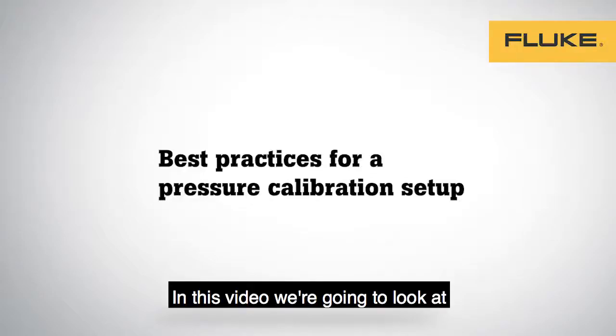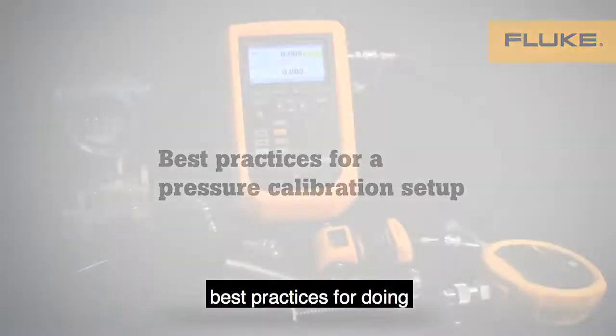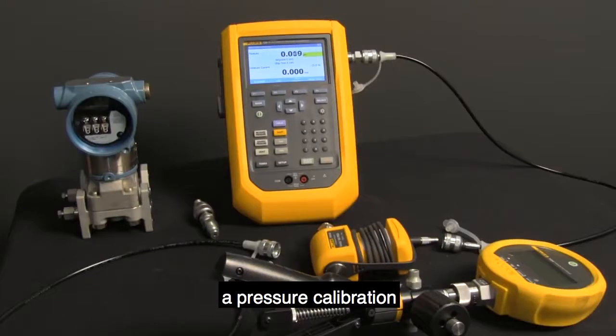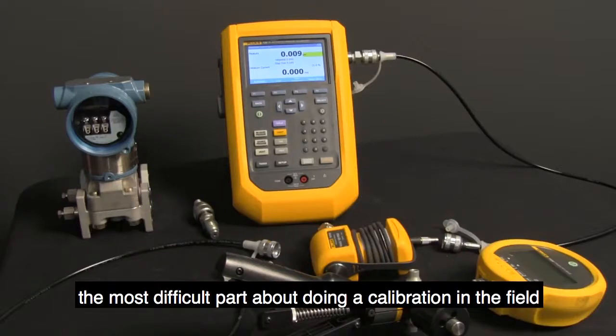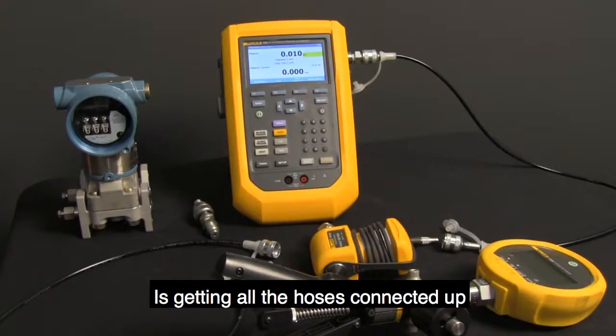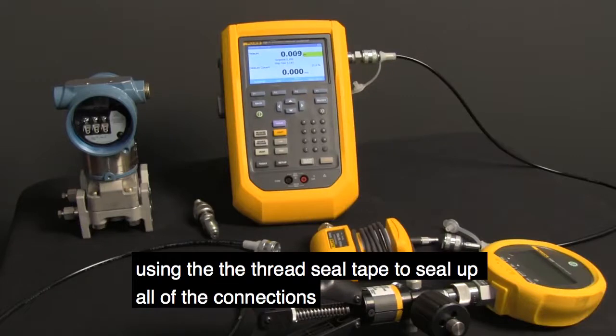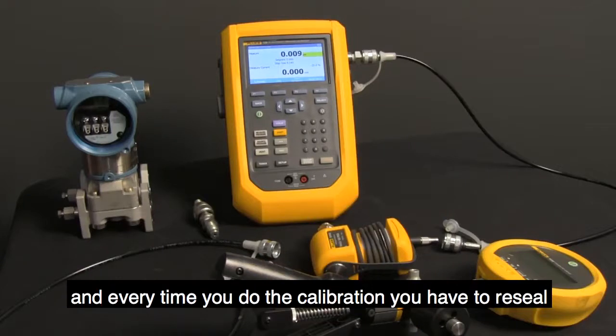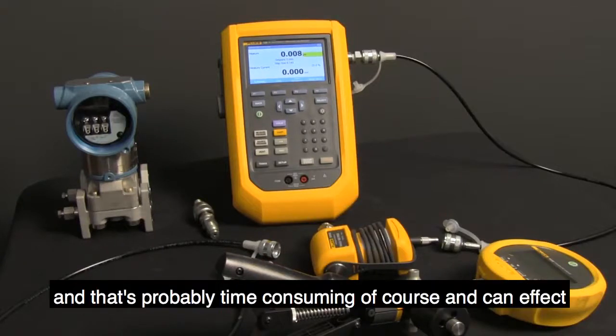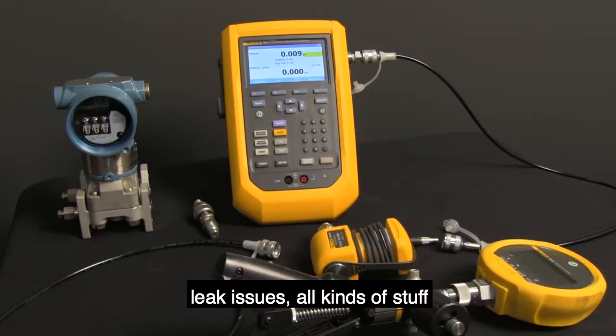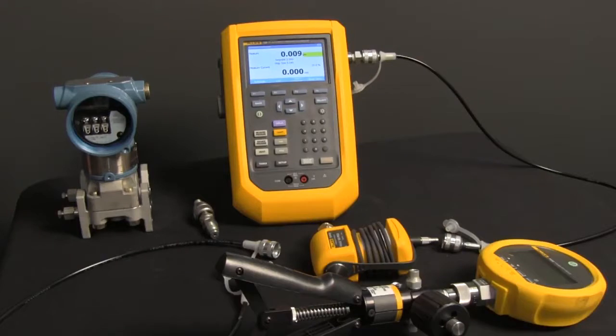So in this video, we're going to look at best practices for doing a pressure calibration. As you guys know, the most difficult part about doing a calibration in the field is getting all the hoses connected up, using the thread seal tape to seal up all the connections, and every time you do the calibration, you have to reseal. And that's probably time consuming, of course, and can affect leak issues, all kinds of stuff.